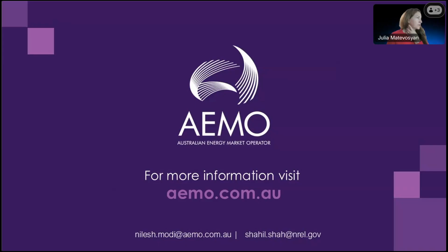The next question is kind of similar, so I'll skip that one. If PMUs were sampled at 30 samples per second, which I think is set at 50, right, how can 18 hertz and higher be detected in real time? That's a very good question. Normally there's the Nyquist criterion, right? So a 50 hertz sample would probably give you a third of 50 hertz with great confidence. But when you look at the samples, you could potentially see very close to 17 hertz. You can still see it. So 50 samples per second doesn't mean that you wouldn't be able to get the 17 hertz oscillation. Some of the figures which I showed were from data at 50 hertz resolution, so 20 millisecond resolution. So it should be able to pick up 17 hertz to a certain extent.